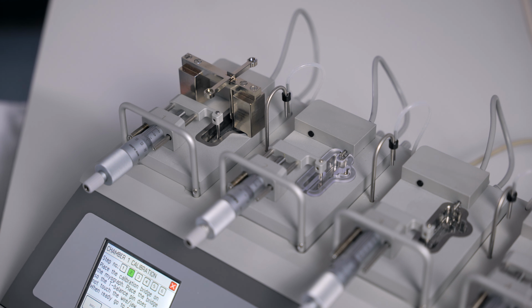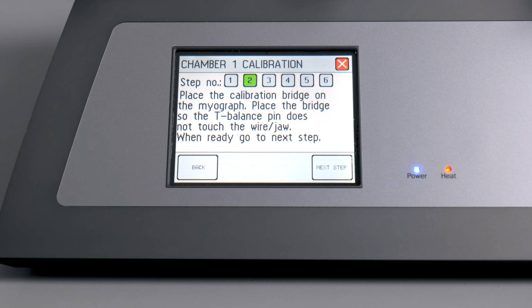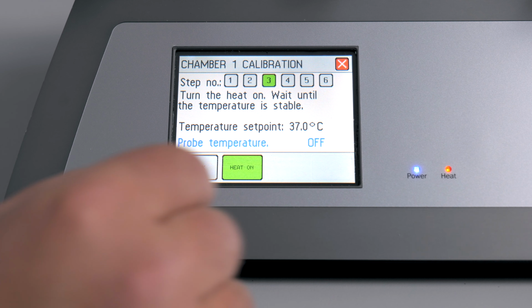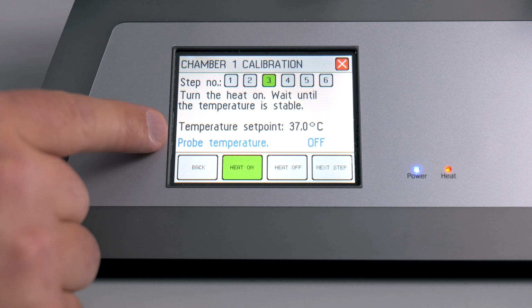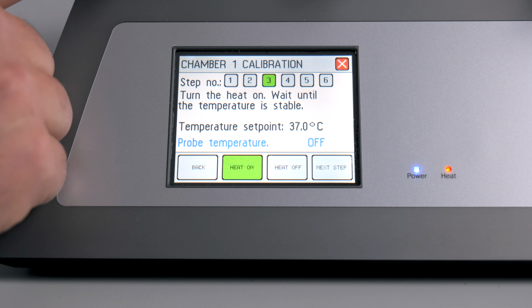The final position of the T-balance should be behind the pin that's attached to the force transducer. It should be in the middle of this pin, but it should not be touching it. Once you have the bridge and T-balance in place, select Next Step. This will ask you to turn on the heat and wait until it is stable. This has been on for 20 minutes, so we can proceed to the next step.